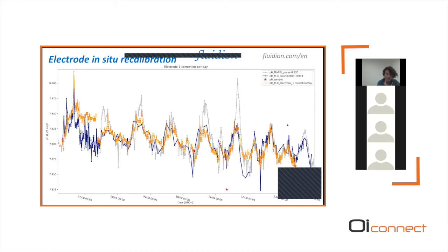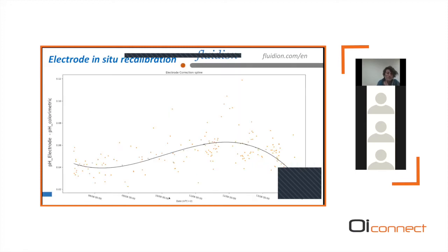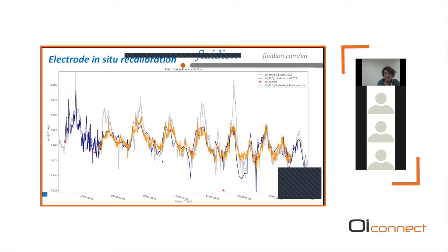some of this effect. But then we looked at how to improve the in situ calibration of the electrode. To do that, we looked at the tendency of the discrepancy between the electrode data and the colorimetric data in time, and obtained a function in time, a spline, that we then apply on the electrode data. By applying this correction, we obtain this result. We removed the first 24 hours of data since it was the equilibration of the electrode. Then you obtain the electrode data, which again fit really nicely the colorimetric analyzer data. And this time we removed some of the discontinuities we could obtain from the previous calibration method.